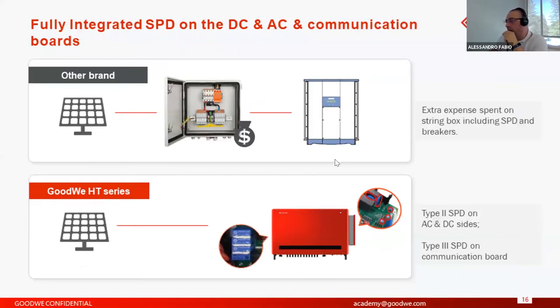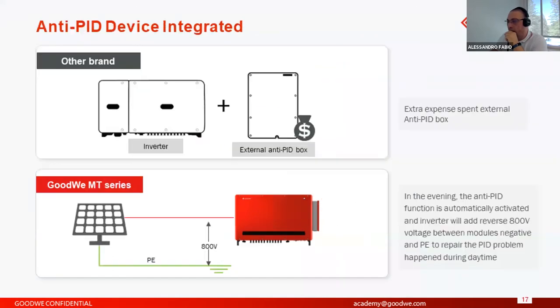What do we mean by less investment? The difference from competitors is more protection and more components inside, for example the SPD protection integrated on the AC and DC side. Also for the communication board we have SPD protection, unlike other competitors that sometimes need external protections or an external combiner box for the PV plants. So everything is integrated inside. We also have the option of an integrated PID device, so we can integrate the PID inside the inverter without an external box or external protection, for example for revamping.